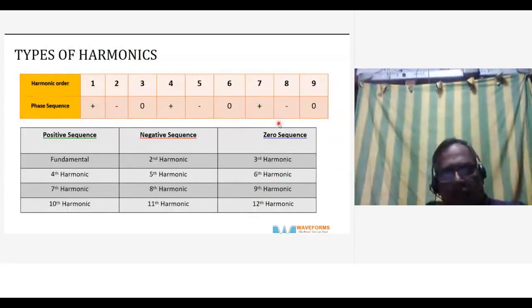So why we have issues with harmonics is because there are different sequences. If the fundamental is positive, the second harmonic is negative, and the third is zero sequence, and then again the fourth is positive, and the fifth is negative, and then it goes on continuously. So you have positive, negative, and zero sequence. Each has different amplitude and phase angles. This is a real issue when dealing with harmonics because they are at different phase angles and different magnitudes and amplitudes. So the issues of harmonics take a serious turn.